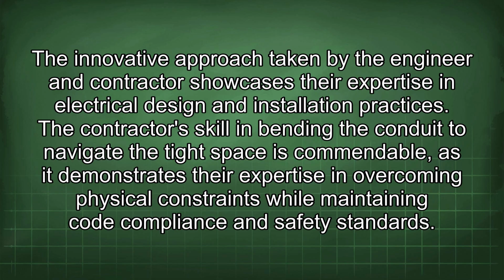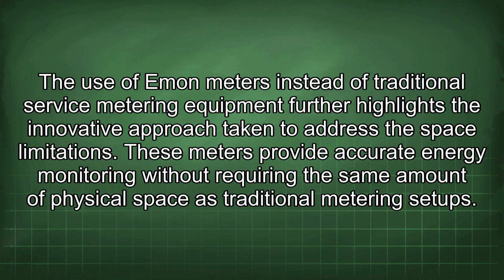The innovative approach taken by the engineer and contractor showcases their expertise in electrical design and installation practices. The contractor's skill in bending the conduit to navigate the tight space is commendable, as it demonstrates their expertise in overcoming physical constraints while maintaining code compliance and safety standards. The use of Emon meters instead of traditional service metering equipment further highlights the innovative approach taken to address the space limitations. These meters provide accurate energy monitoring without requiring the same amount of physical space as traditional metering setups.